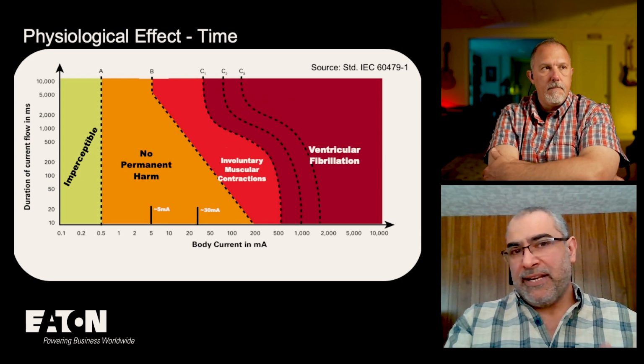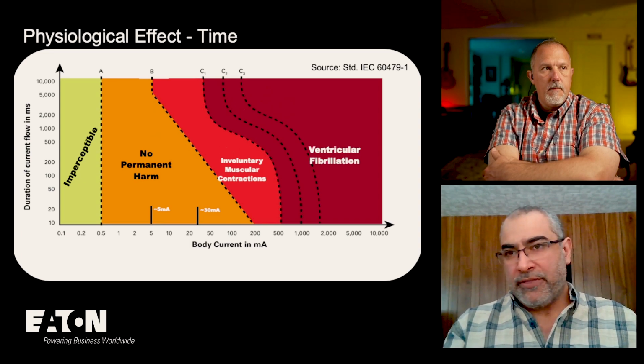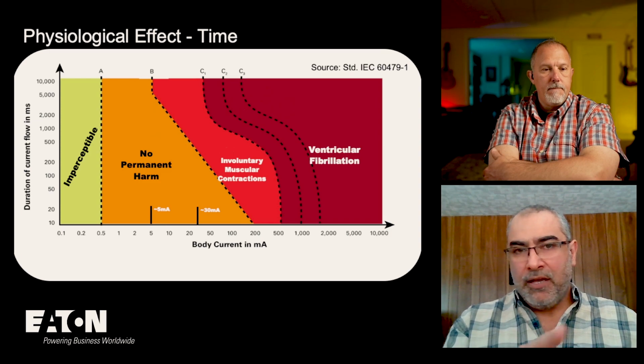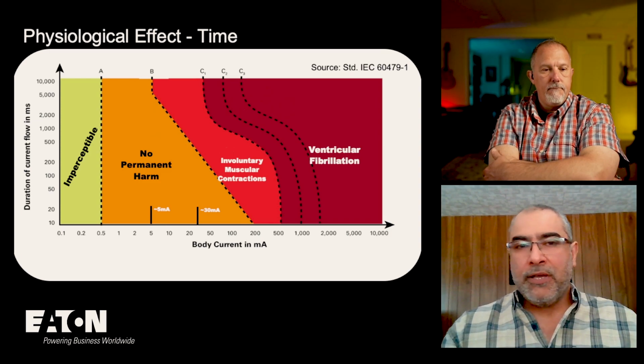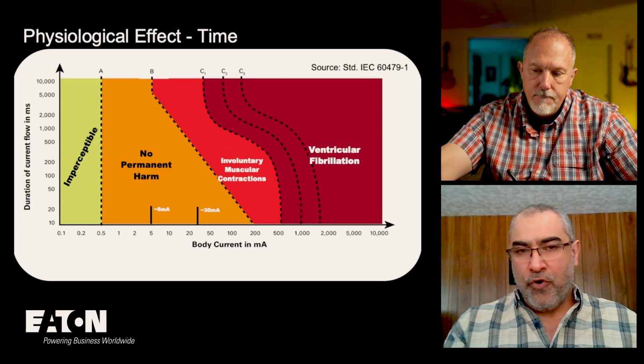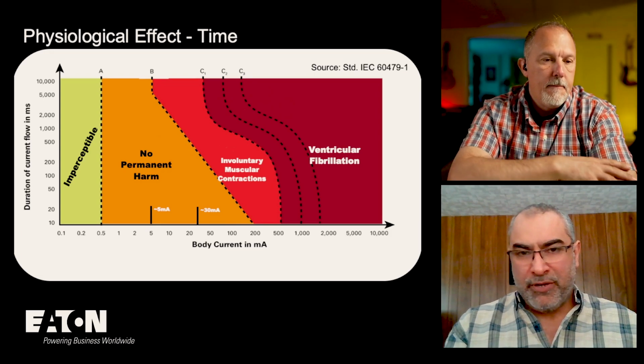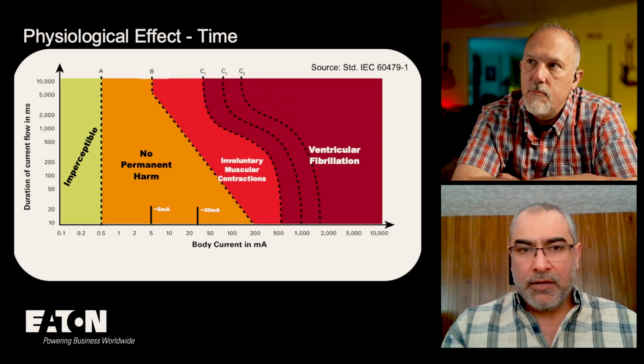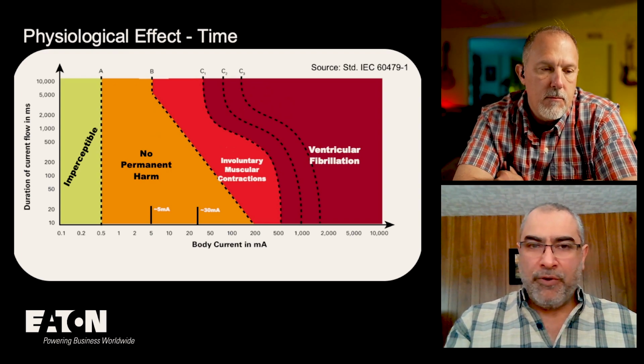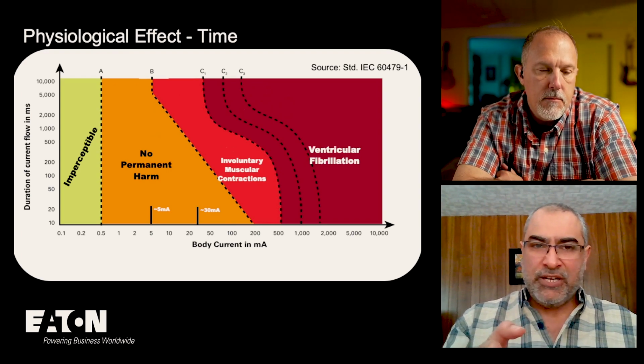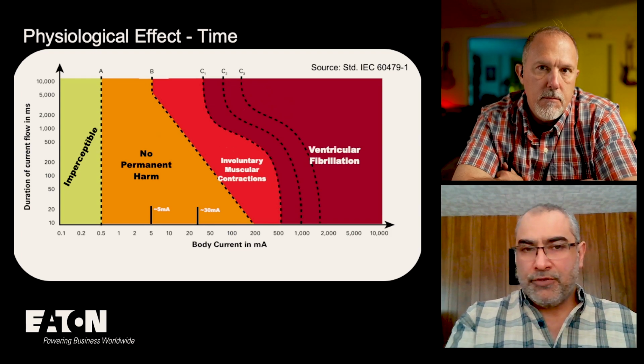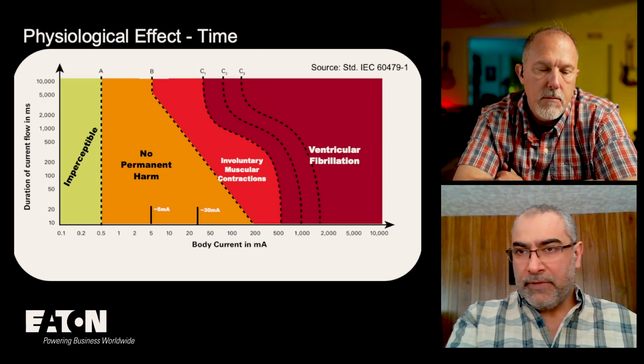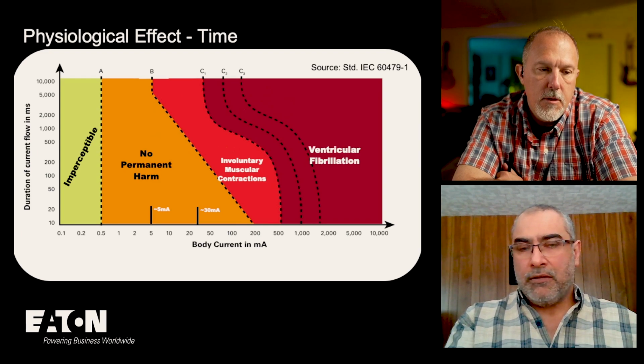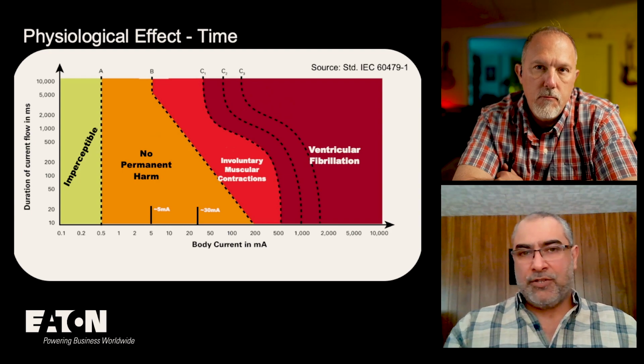But the story starts getting different as you go further right on the x-axis to higher current - the dotted line B has more of a slope. So if you go vertically for the 20 or 30 milliamp line, you start transitioning from the orange zone, which has no harm, into the light red zone, which involves muscle contraction.